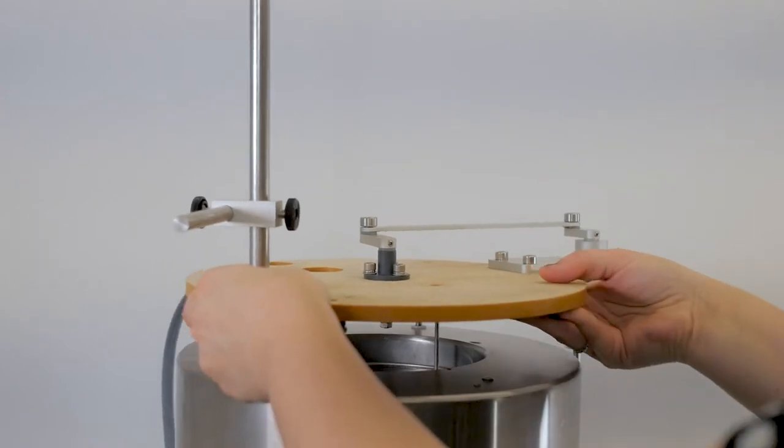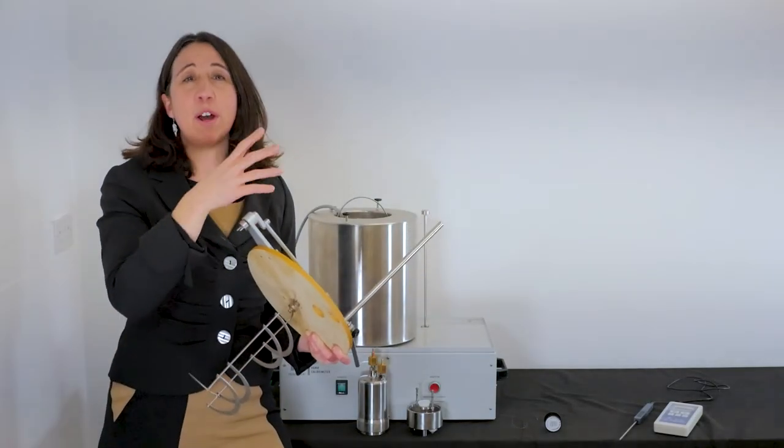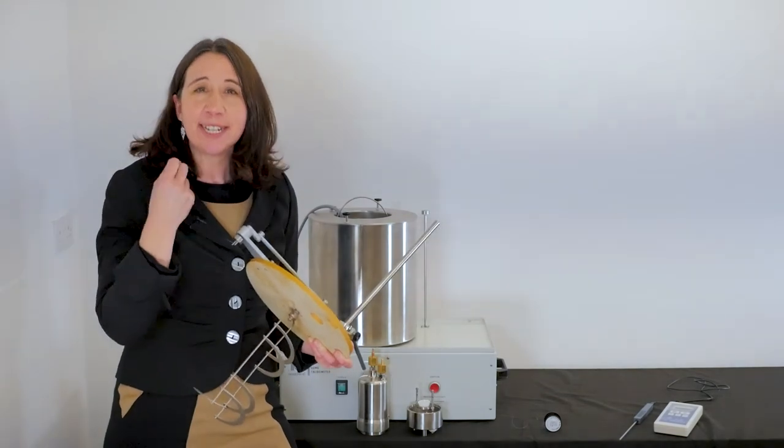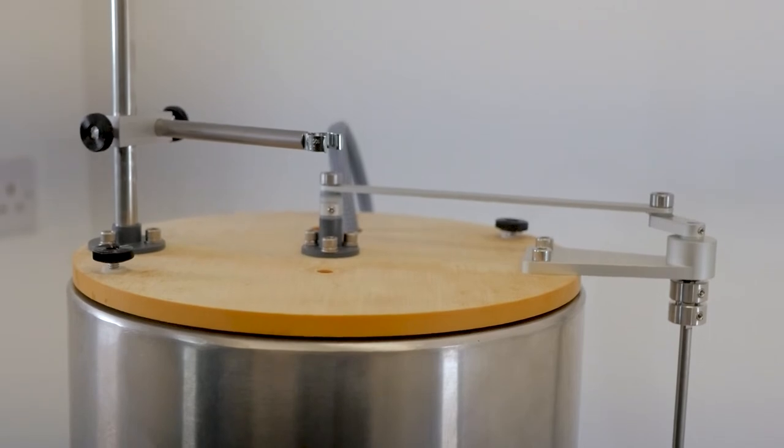The stirrer mixes the water within the bomb vessel to balance the temperature throughout to avoid hot and cold spots for a stable accurate spot measurement of temperature that is calculated into calorific value.